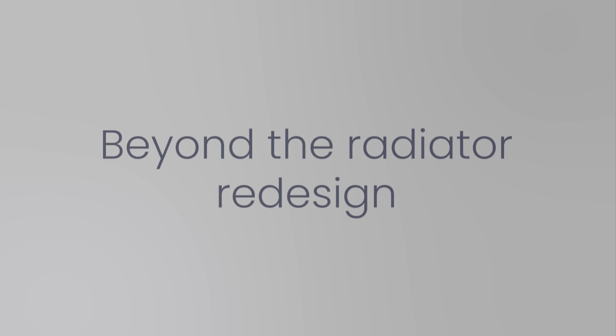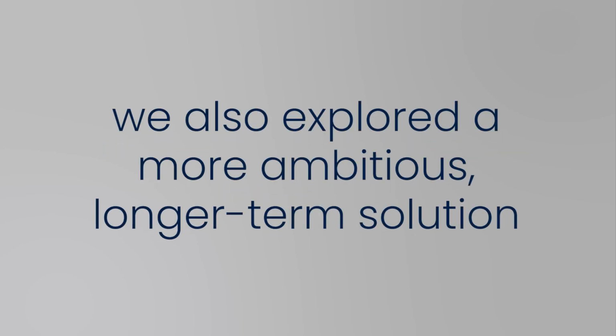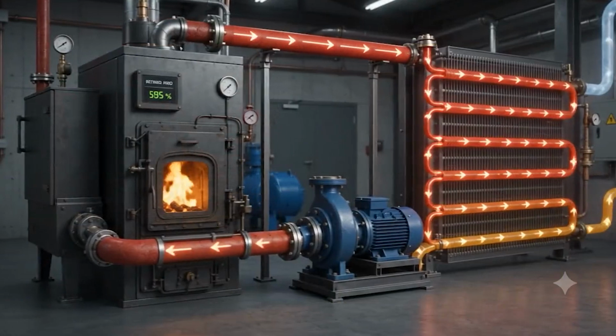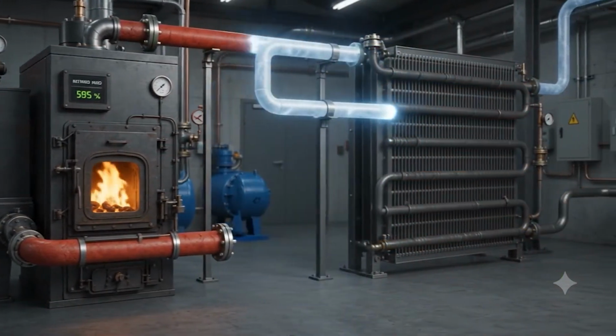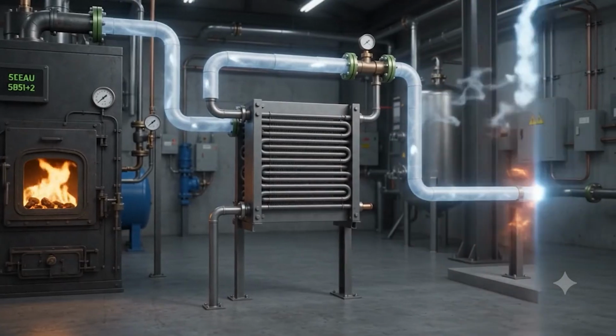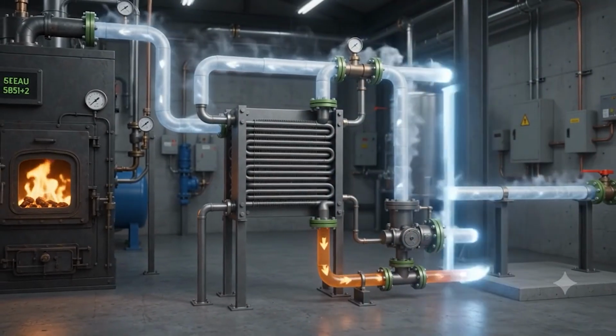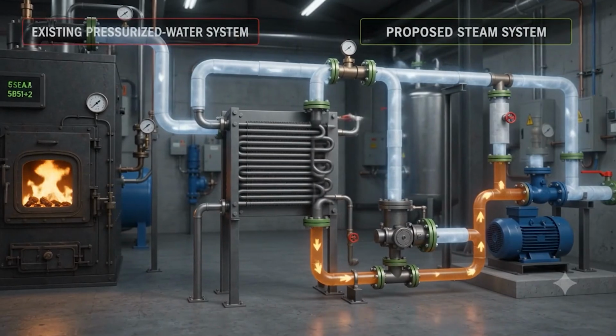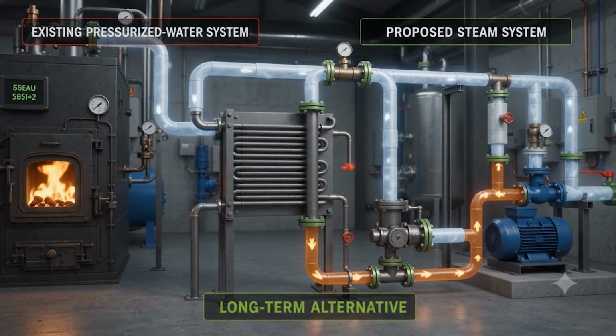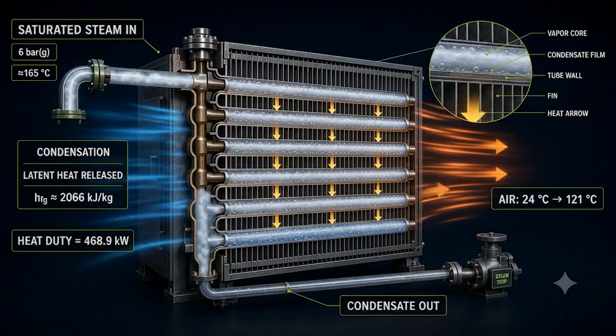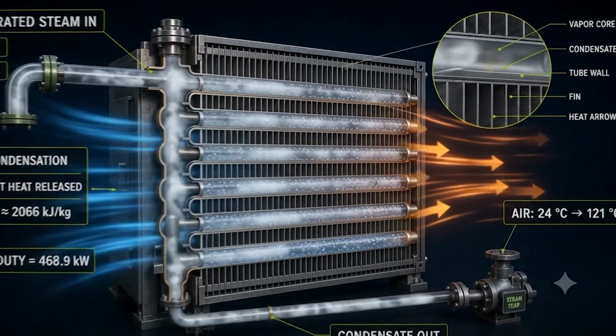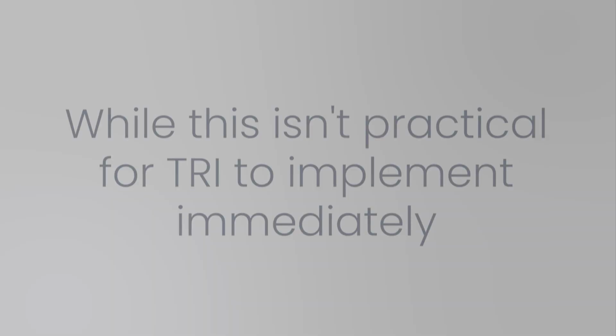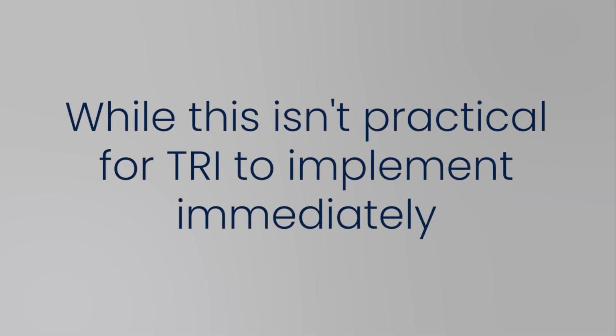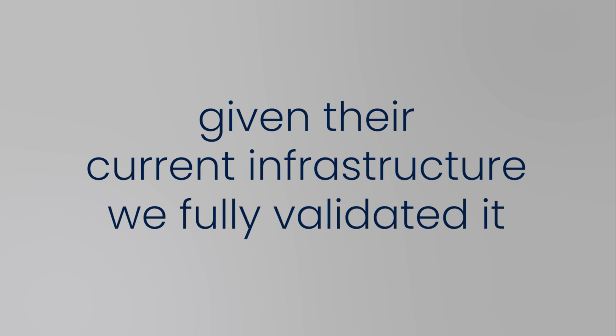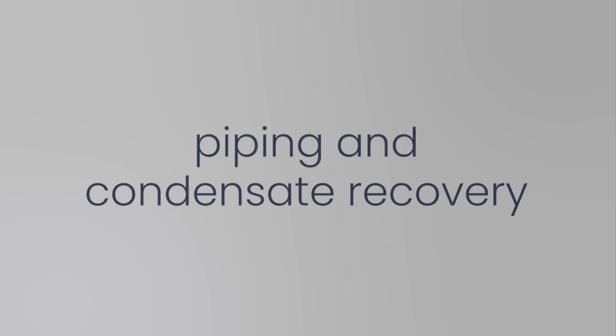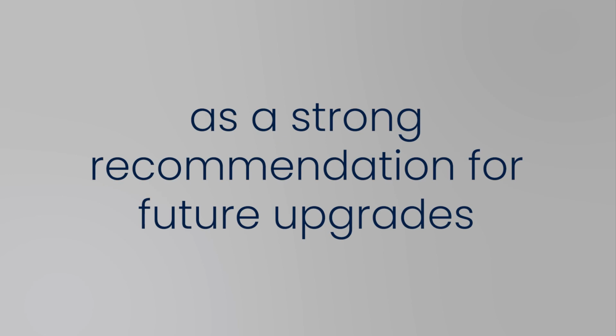Beyond the radiator redesign, we also explored a more ambitious, longer-term solution: converting the entire system from hot pressurized water to steam. At 6 bar gauge pressure, steam's latent heat of vaporization can deliver the same heat duty using a smaller, more efficient heat exchanger. Our calculations showed this approach could reduce biomass fuel consumption to an estimated 214.5 kilograms per hour for the same drying output. While this isn't practical for TRI to implement immediately, given their current infrastructure, we fully validated it, from heat exchanger sizing to piping and condensate recovery, as a strong recommendation for future upgrades.